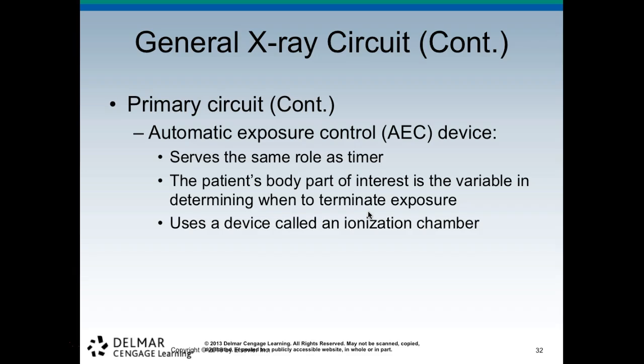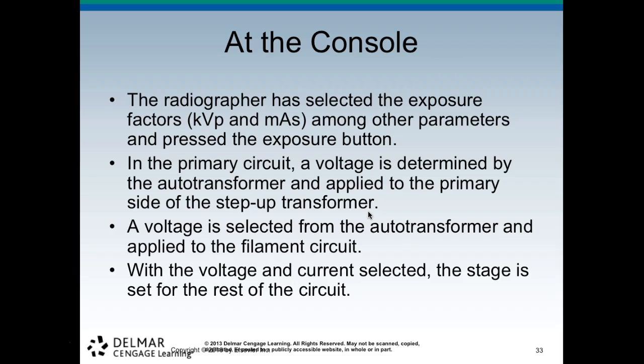All right, your AEC device serves the same role as the timer. The patient's body part of interest is the variable that determines when to terminate the exposure. It uses a device called an ion chamber to measure the amount of radiation and will terminate the exposure. And we're going to talk about what the backup timing needs to be when you set the AEC.